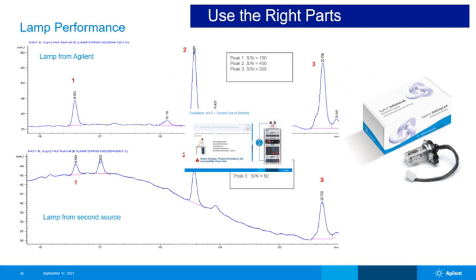The importance of the lamp. Here we have an example comparing a lamp from Agilent with a lamp from another source. As you can see, signal to noise is significantly better with the Agilent lamp. Also, the baseline drift is a real problem with this competitor lamp. So the lamps might look the same, but they are definitely not the same. Agilent lamps have been designed and optimized for each detector, which ensures best chromatographic results.